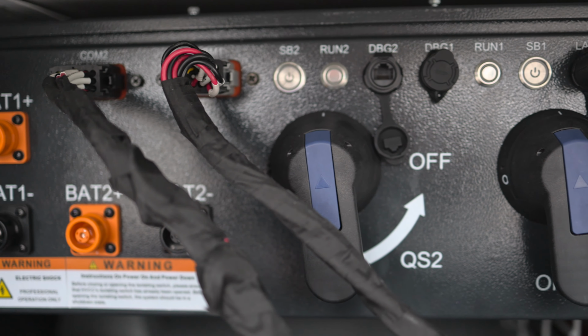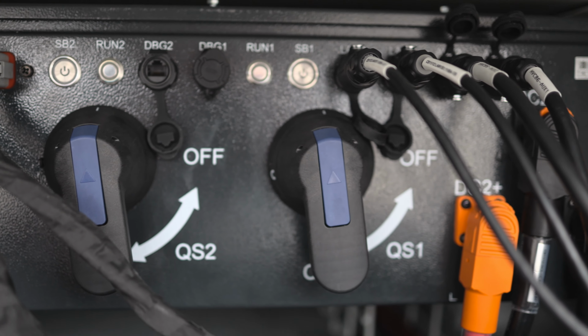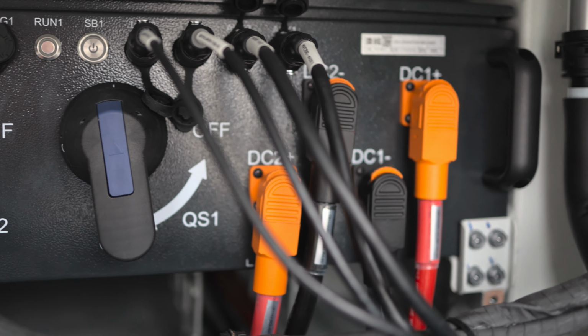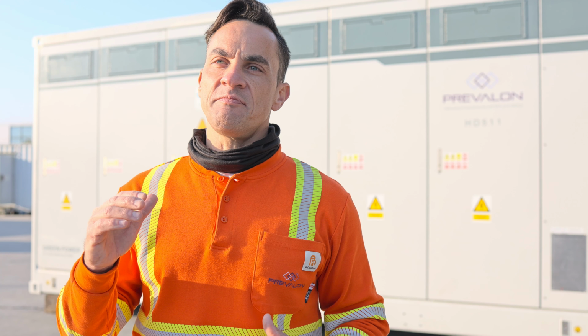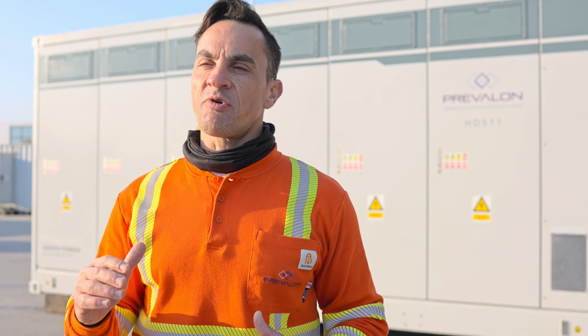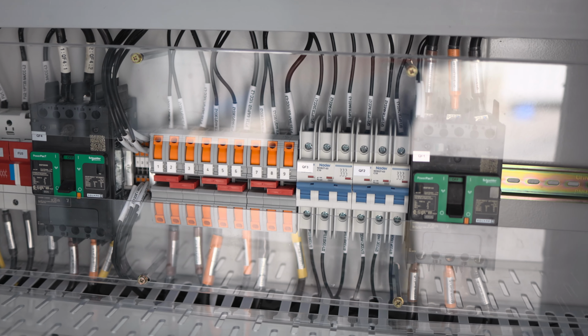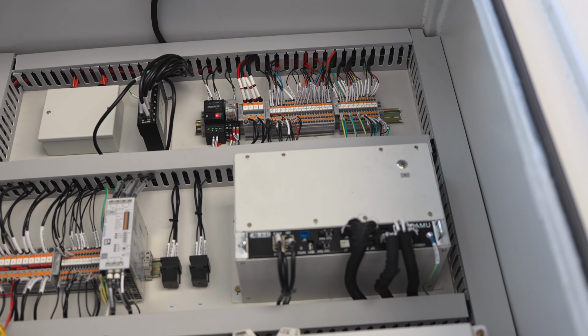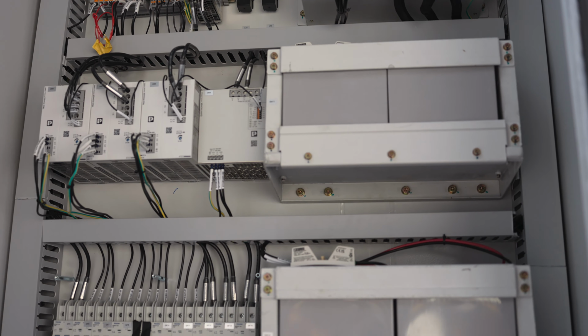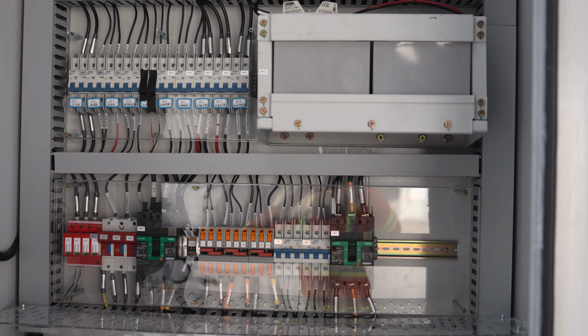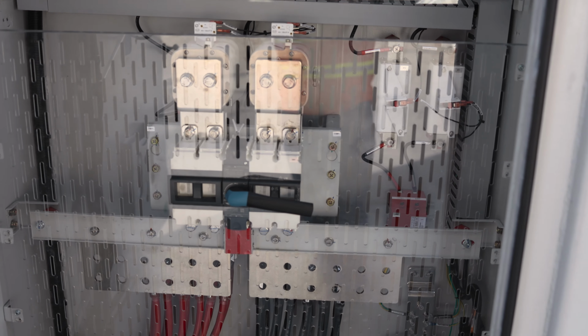The enclosure has 3 separate compartments that are isolated from each other. The chiller compartment hosts the integrated chiller, which delivers liquid cooling to the battery modules and electrical compartment heat exchanger. The electrical compartment hosts power supplies, UPS, and auxiliary power distribution components. It is environmentally controlled to maximize the life of sensitive components.